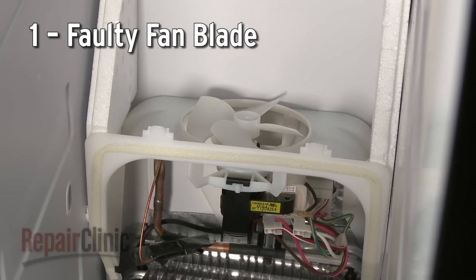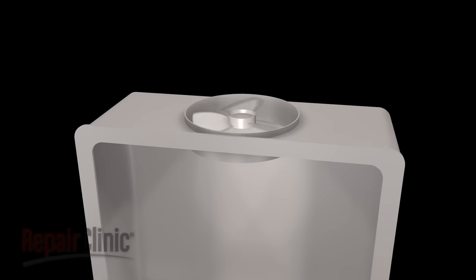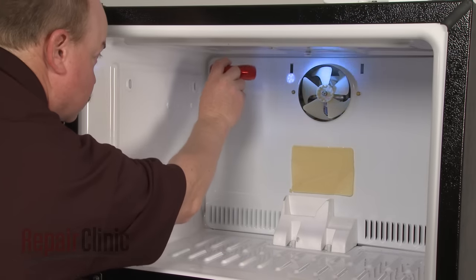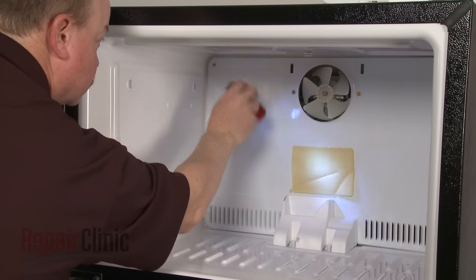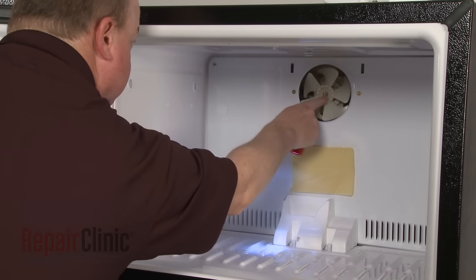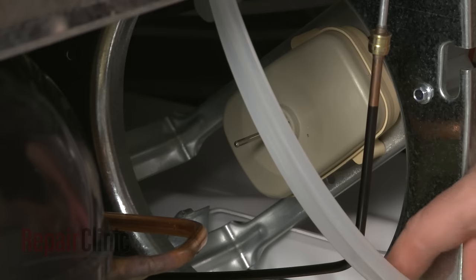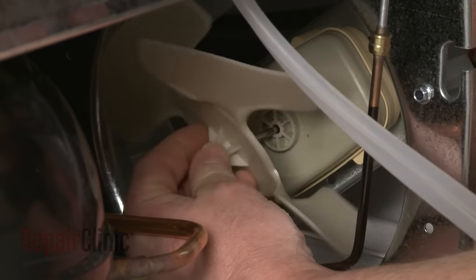The condenser fan motor blade or evaporator fan motor blade could be damaged or scraping against a panel or bracket. You should check both blades to determine if they are obstructed or if they can turn freely. Both the condenser fan blade and the evaporator fan blade can be replaced independently of the motors.